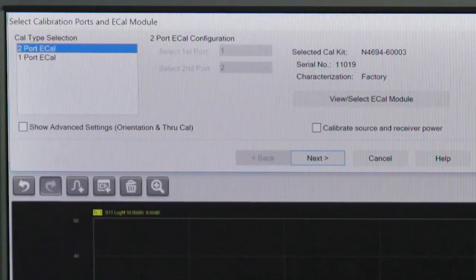We're going to do 2-port E-cal and leave the default settings. Select Measure. Once the calibration is complete, you will see a message like this pop up on screen showing that the calibration has been saved to the channel.